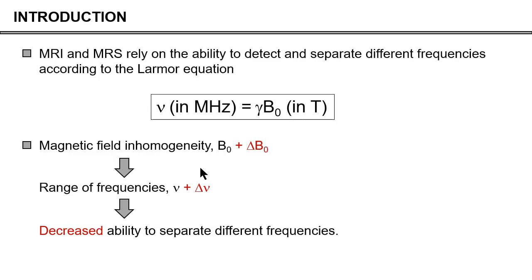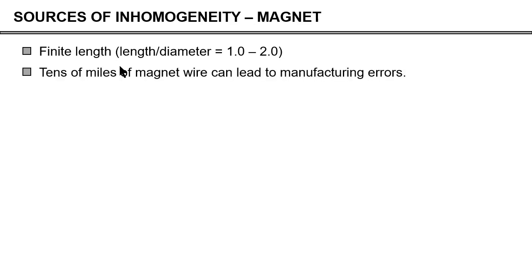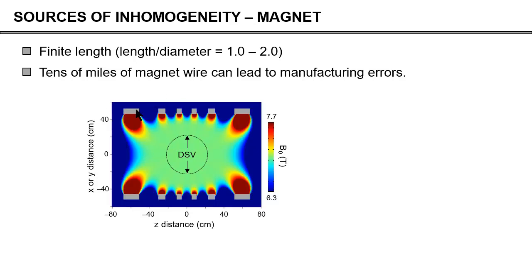So why do we have inhomogeneity? The previous speaker already showed a few examples. The magnet is certainly by far the most important one. If you have an infinitely long solenoid coil, you're going to have a perfectly homogeneous magnet. However, an infinite coil is not practical. So in reality, the length is finite, and that will introduce inhomogeneity. In addition, you're going to have many miles of magnet wire, and if they're not laid out perfectly, you're going to get manufacturing errors and inhomogeneity.